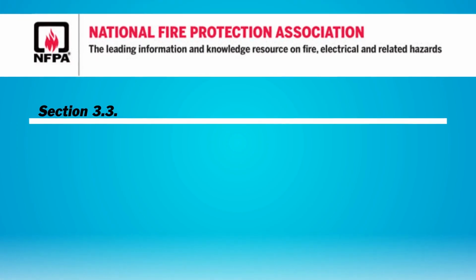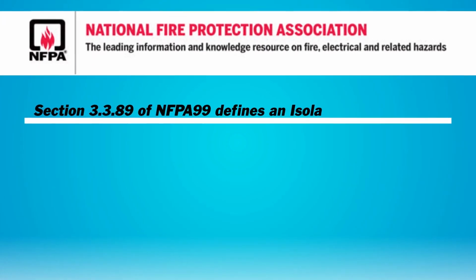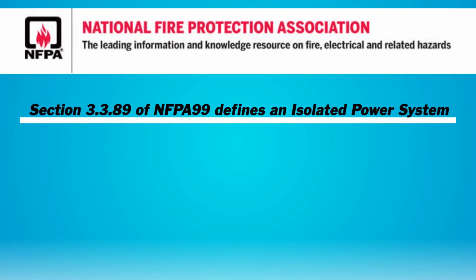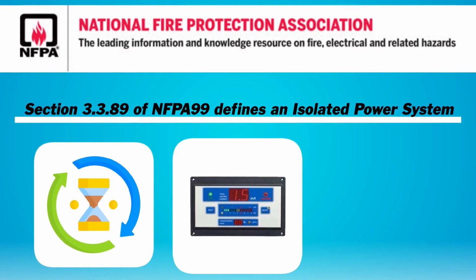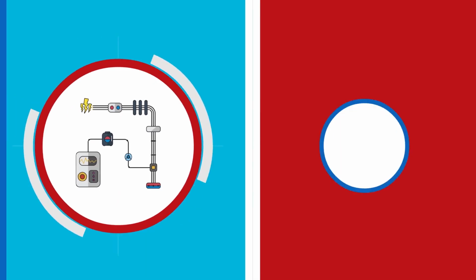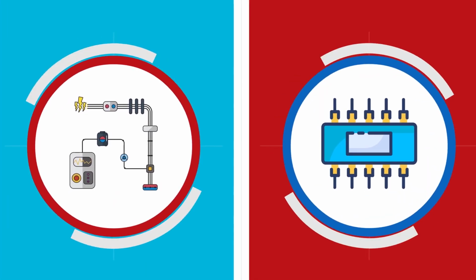Section 3.3.89 of NFPA 99 defines an isolated power system as a system comprising an isolation transformer or its equivalent, a line isolation monitor, and its ungrounded circuit conductors.